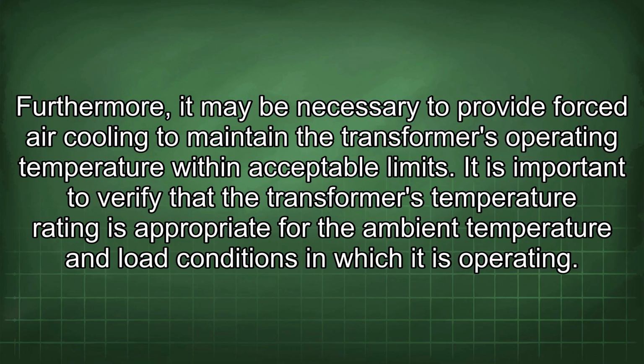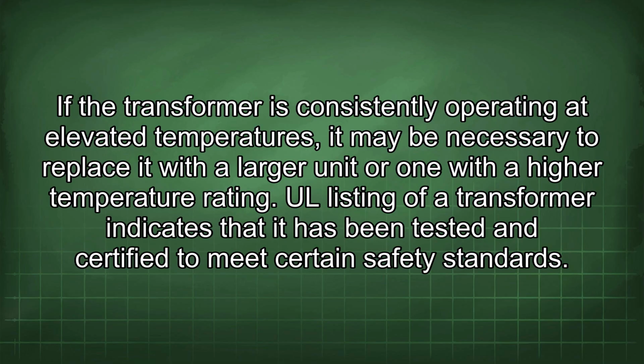It is important to verify that the transformer's temperature rating is appropriate for the ambient temperature and load conditions in which it is operating. If the transformer is consistently operating at elevated temperatures, it may be necessary to replace it with a larger unit or one with a high temperature rating.